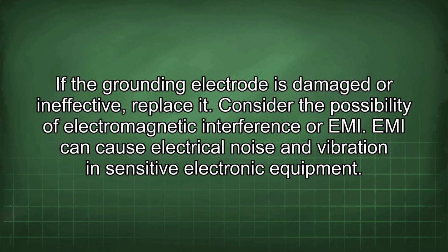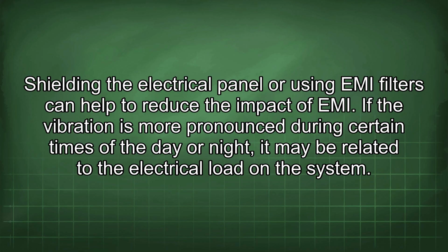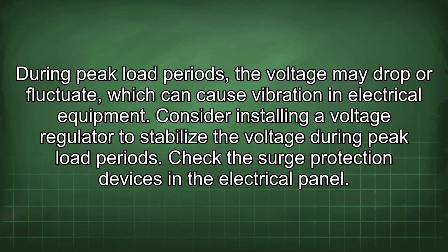Consider the possibility of electromagnetic interference or EMI. EMI can cause electrical noise and vibration in sensitive electronic equipment. Shielding the electrical panel or using EMI filters can help to reduce the impact of EMI. If the vibration is more pronounced during certain times of the day or night, it may be related to the electrical load in the system. During peak load periods, the voltage may drop or fluctuate, which can cause vibration in electrical equipment. Consider installing a voltage regulator to stabilize the voltage during peak load periods.